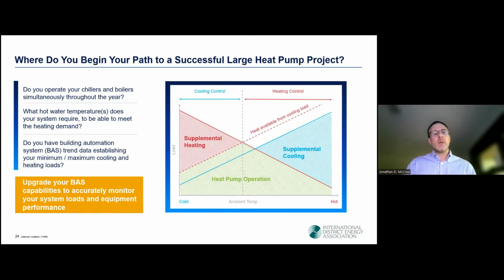throughout the year. And once you've assembled that load information, at this point, I'd recommend engaging a heat pump manufacturer, either directly or in conjunction with your consulting engineer, and take a look at what sizing might make sense for the machine or machines that would fit with your system. In principle, you want to get the most benefit you can by maximizing all the heating that you can get from the heat pump, but it's very important to select it carefully. And as we've noted, consider the minimum heating and cooling loads when you're picking the heat pump.